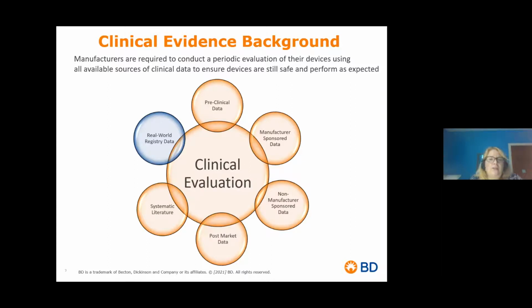The frequency of the evaluations depends on the risks associated with the device. So with our surgical mesh and fixation devices, they are the higher class 3, so we have to do these annually. There are a variety of different sources of clinical data that we have to collect and analyze in these clinical evaluation reports. The preclinical data from any internal testing that we've done for our verification, validation, biocompatibility, any type of comparable studies that we're doing, manufacturer-sponsored data, either published or unpublished clinical studies, non-manufacturer sponsored studies that we can get any results from clinicaltrials.gov or the WHO database. The EU also has a registry for clinical trials as well.